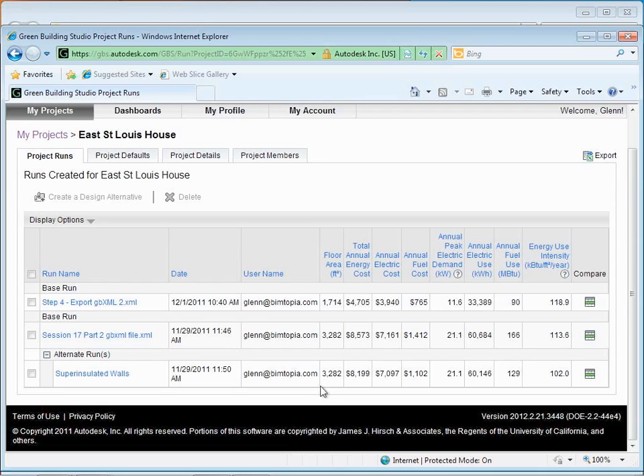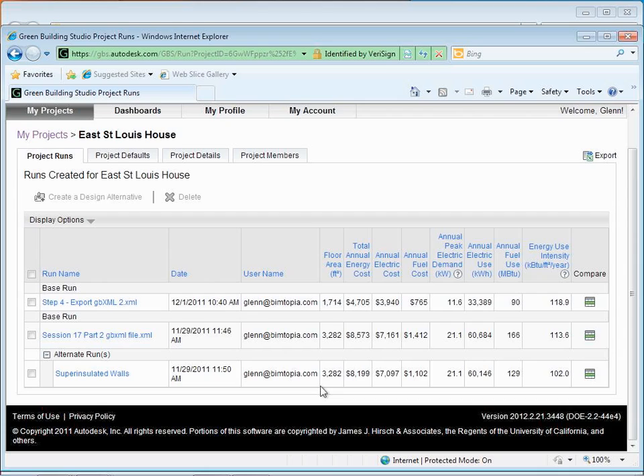It is reported right here. So basically, here's the initial one that we did the other day. It had an energy use intensity of 113.6. By super insulating the walls, we got it down to 102. Now, interesting things sometimes happen along here because as you go through and compare things, sometimes you get odd effects.